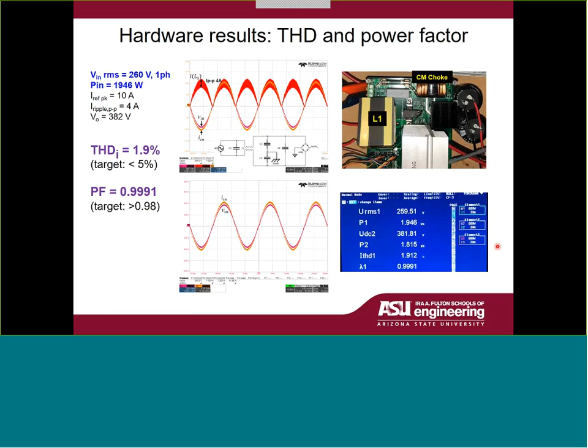The THD is as low as 2%, whereas our target is just less than 5%, so we are well above meeting that target. The power factor, for all practical purposes, is just unity, and that is confirmed by all of these power analyzer waveforms.